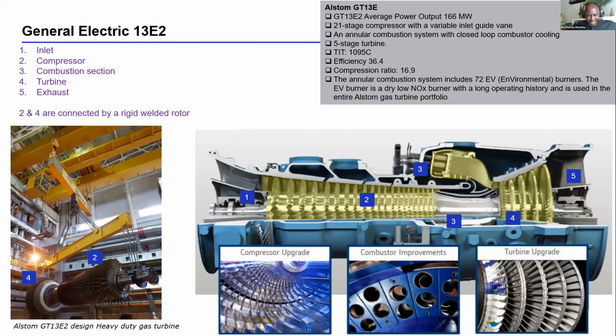And also the rotor of the GE, GE recommends that at 200,000 hours, you should replace the rotor. But what Siemens and Alstom do is, at 100,000 hours, they do what they call a lifetime extension inspection. So they inspect the rotor and increase the life of it, by doing a lot of modification or material or whatever.